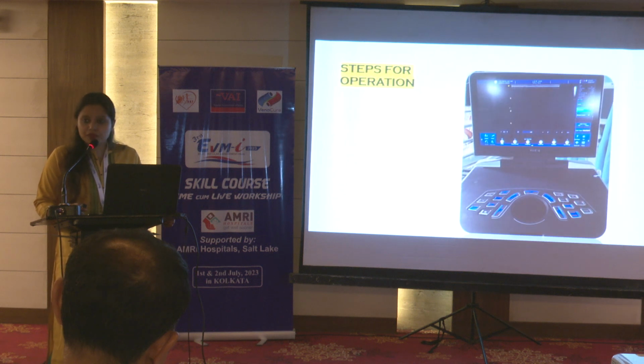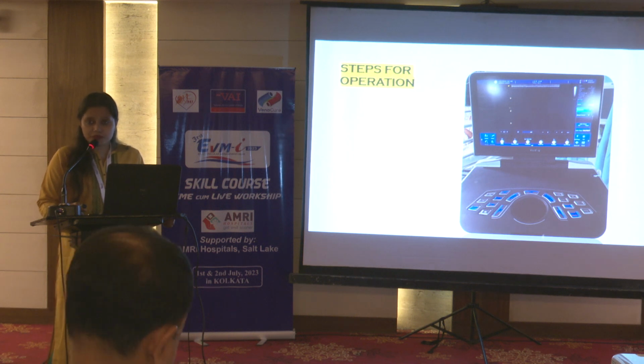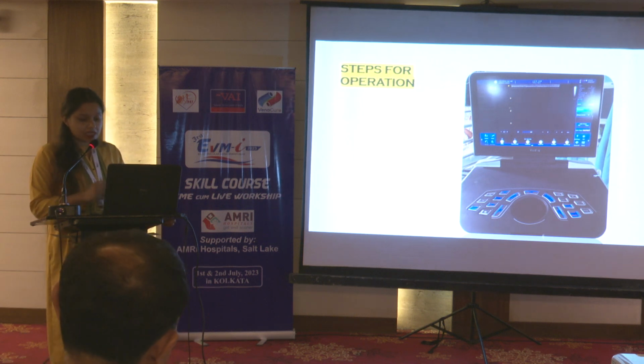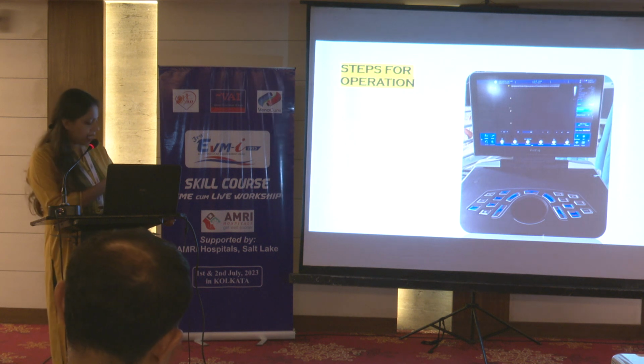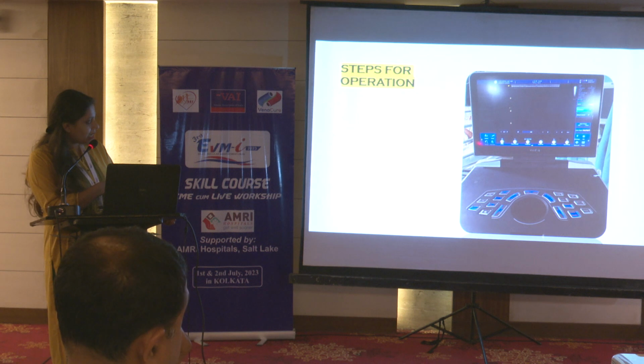Now, after switching on, the machine gets into the scanning mode. Now, this is a universal mode. The scanning mode usually can be differentiated by the probes we use. Now, after getting into the scanning mode, we need to select the probe. The probe is on the left-hand side of the screen. We have the probe selection.